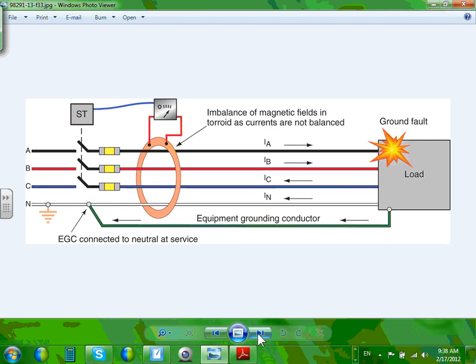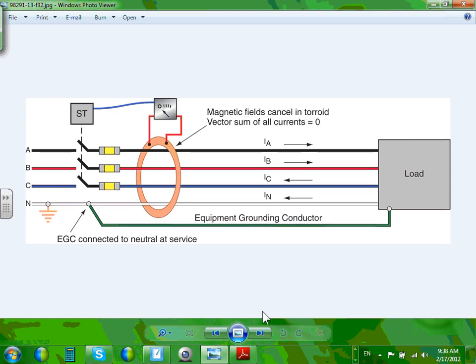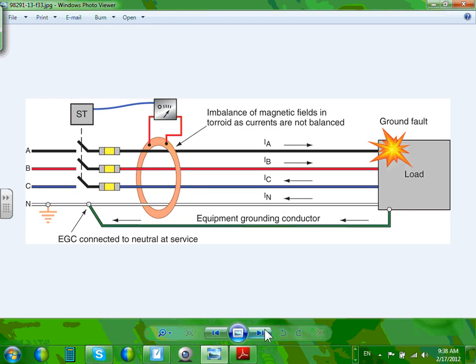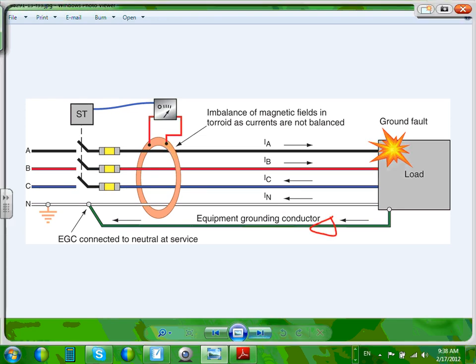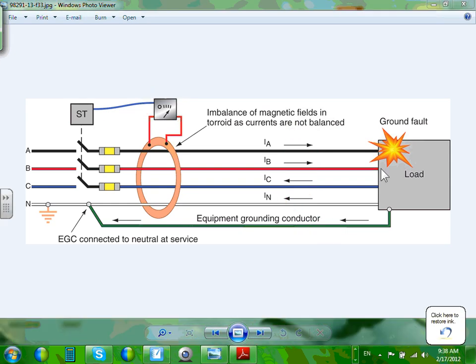Sum of conductors equals 0. I don't know if you guys can see how it looks. If the system is up and running, A, B, C, D, the neutral, all of them are going to sum to 0, right? Nothing is happening. The minute that you have a ground fault, some of the current will be going back to the ground. Then it will sense that there is a difference in the current, unbalanced, not balanced here. And you could trip, you could alarm. You don't have to trip. You could send a signal to your cell phone saying you have a ground fault. You could do anything you want with the ground fault.